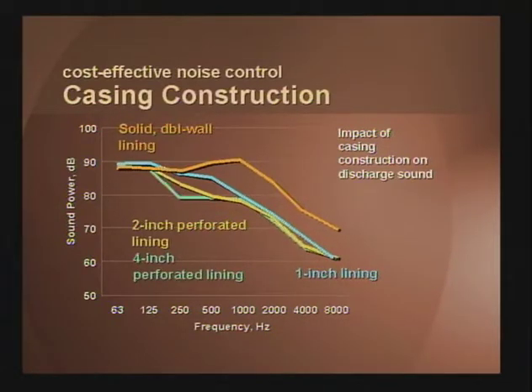Add 2 inches of perforation or 2 inches of insulation, you get even additional pull down primarily in the 500 hertz area. 4 inches of insulation, additional pull down in the 250 hertz area. If it's important to get the 250 hertz down, 4 inches is the right route to go. But consider the cost of the casing options relative to the source options we talked about earlier when cost optimizing your system.